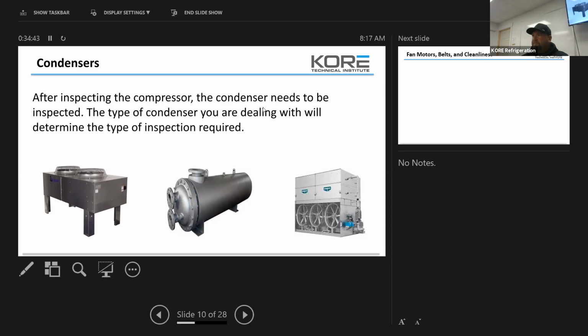I've seen those compressors, the big one. This condenser? Yeah, over in Beaver. Yeah, you're going to see, these are extremely efficient. The only problem is if you're dealing in a region that has water restrictions, because you're using water for evaporation here to transfer the heat as you're condensing. So we're going to see those a lot in the South.